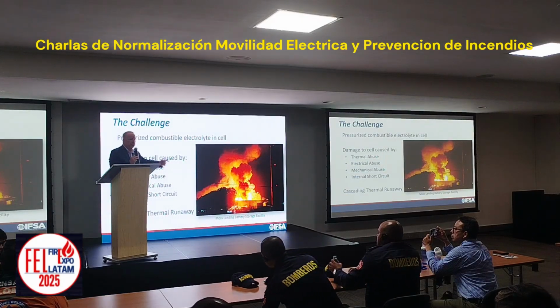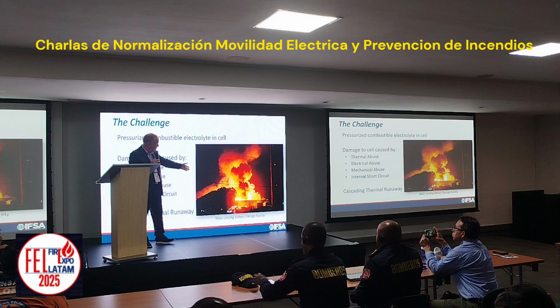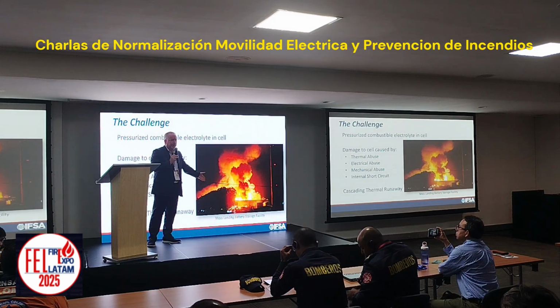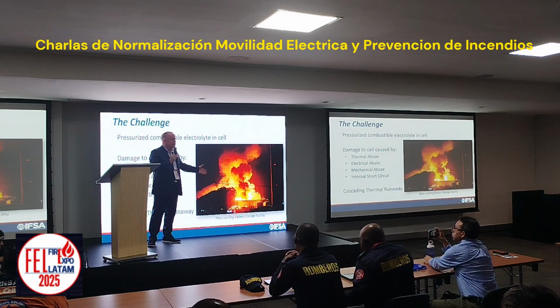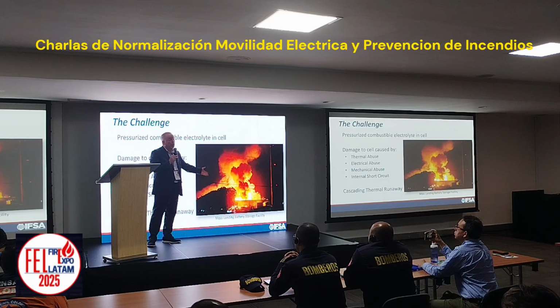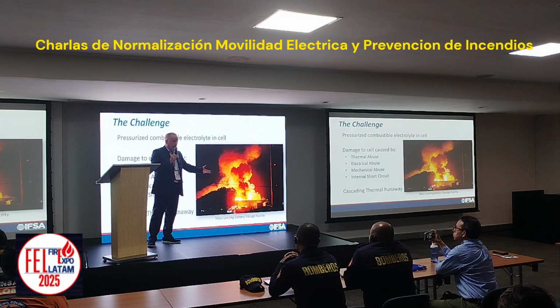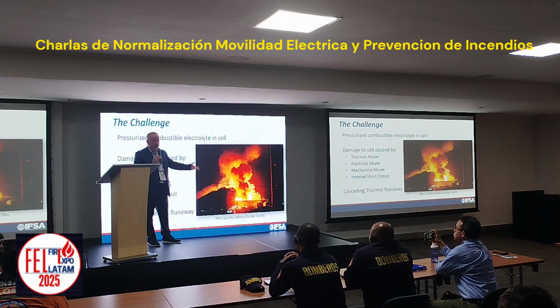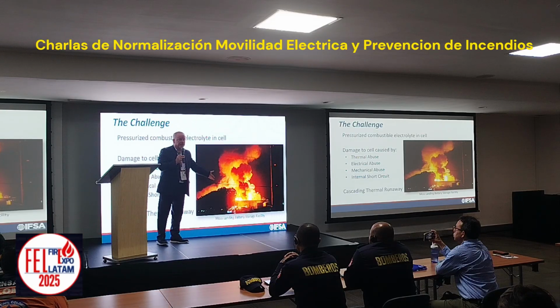Now, what can result from those small battery fires is exactly this right here. This is, or was, a large battery storage facility in Northern California that was not protected by automatic sprinklers. It basically suffered cascading thermal runaway through damage to the batteries that were in it.